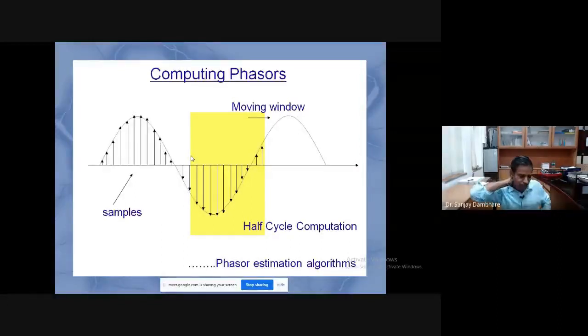These phasors are then used for protection purposes. A phasor has two values, magnitude and angle, and these phasors are computed based on previous data. You can see here the window where you collect data over a half cycle, and computation of the phasors is based on the data collected in that half cycle. Whenever a new signal comes, the last signal is asked to exit, and the window size is kept constant. This is what is called the moving window, moving forward as the signal advances.